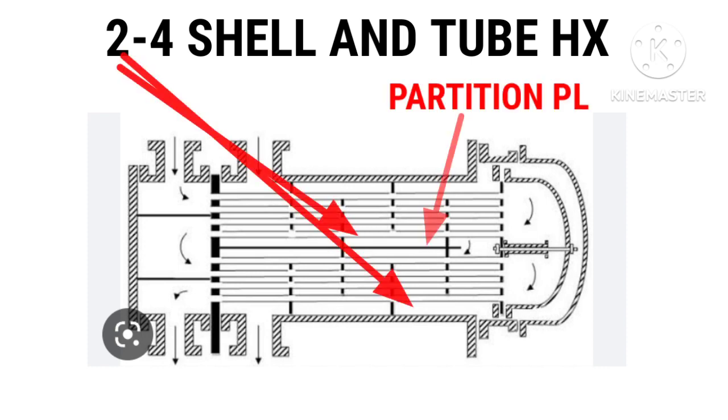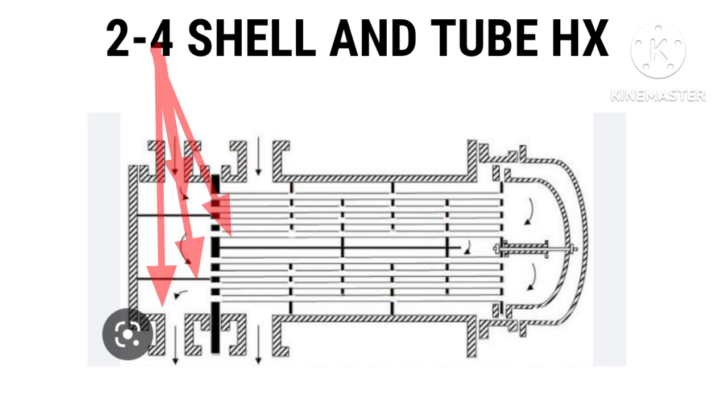What is two-four heat exchanger? The first number two means the fluid of shell-side flows twice in shell-side due to one side partition. Also, second number four means fluid of tube-side flows four times in heat exchanger due to two partitions as shown in figure.